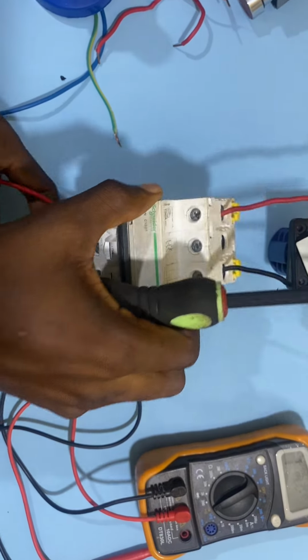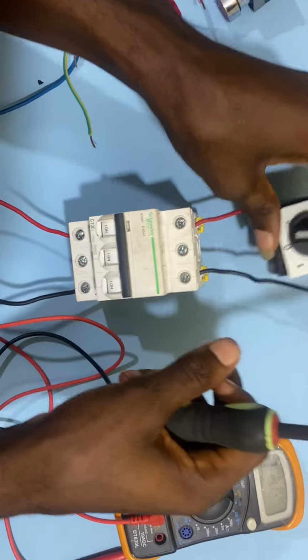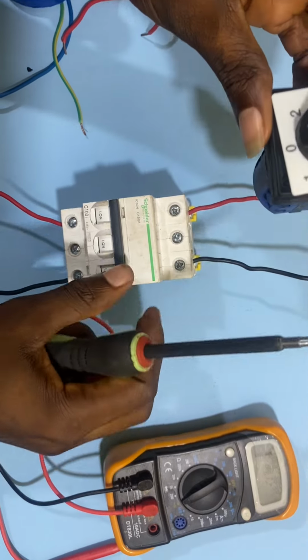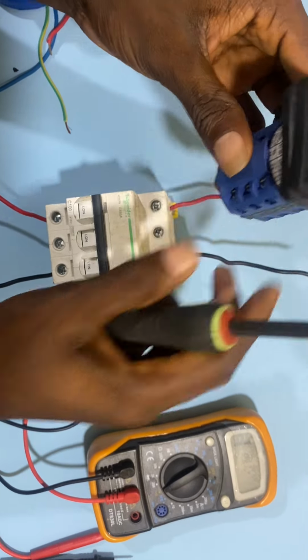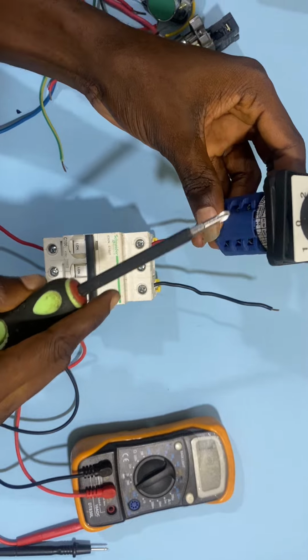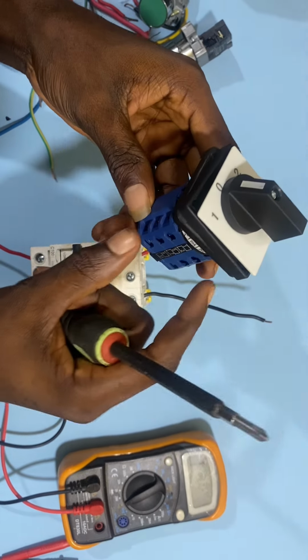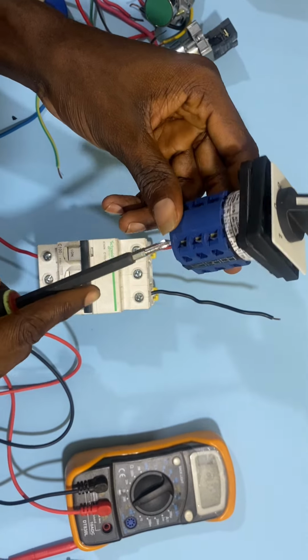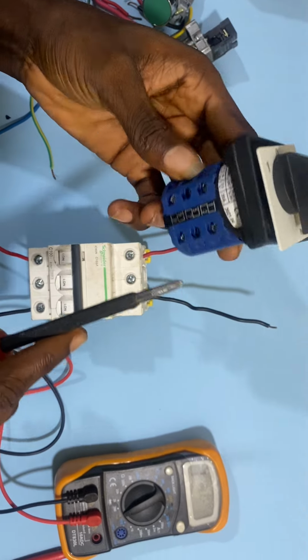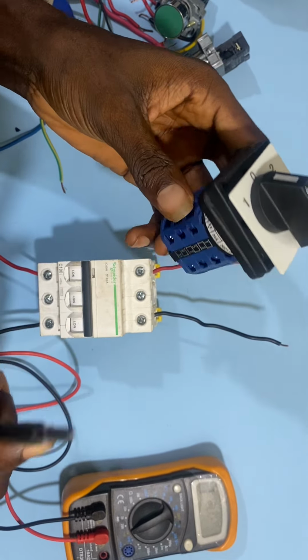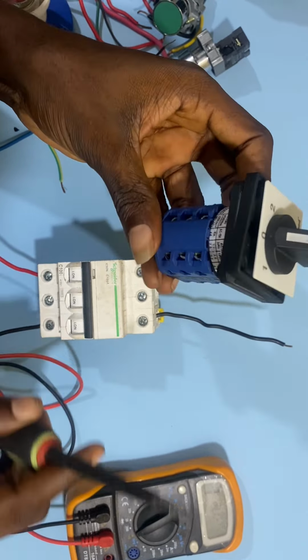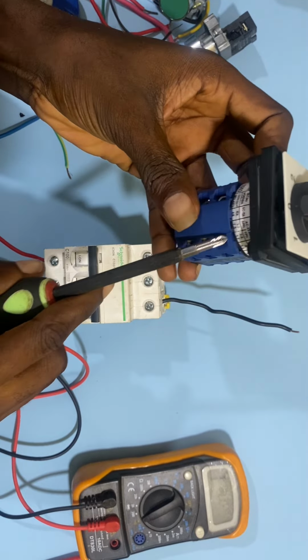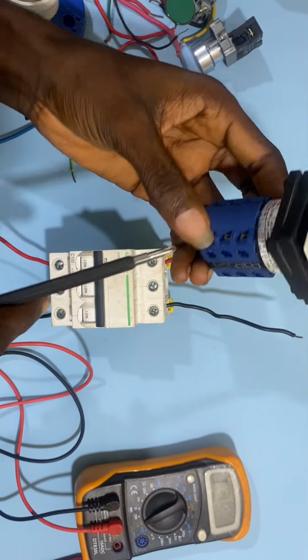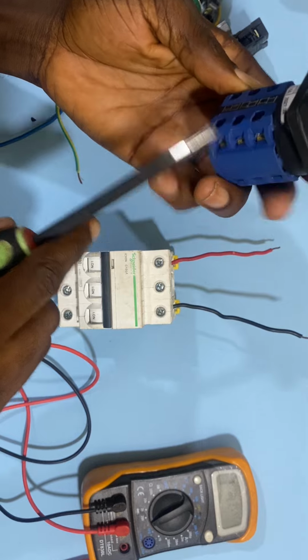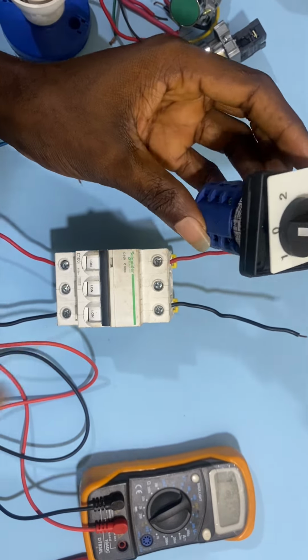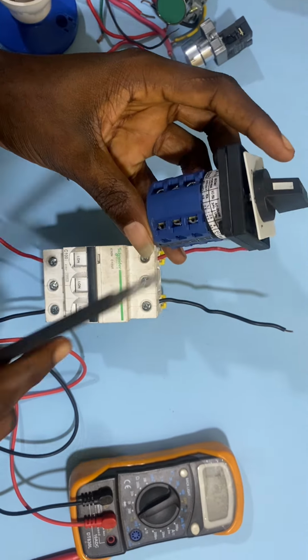So I need to connect from the circuit breaker down to the selector switch. So how do I do that? Since I know that if I input here, I'm going to get the output here. This switch uses three phase, but I want to use single phase to connect it, and I want to control with only one voltage supply. But in your case, you can use your generator on this side. That will be your generator input and your generator output. You can put your NEPA input here and your NEPA output. But in this case, I want to use only NEPA input.